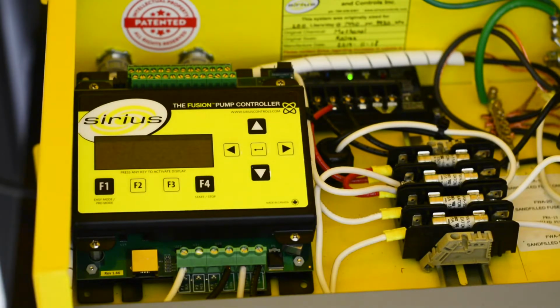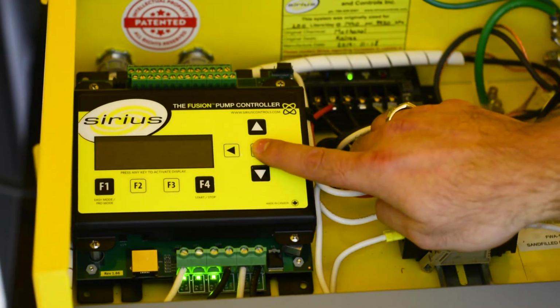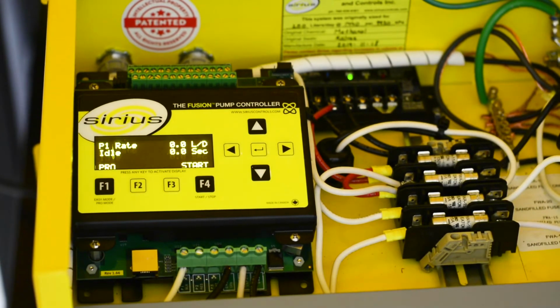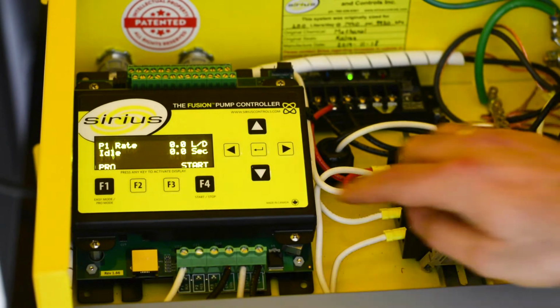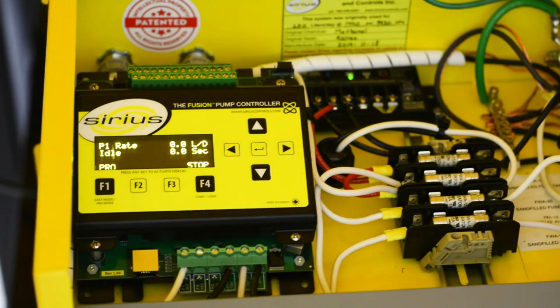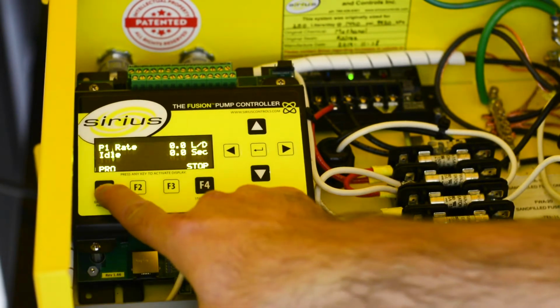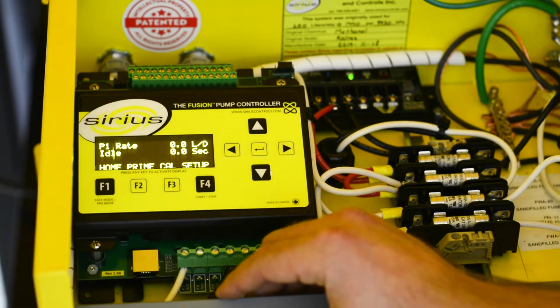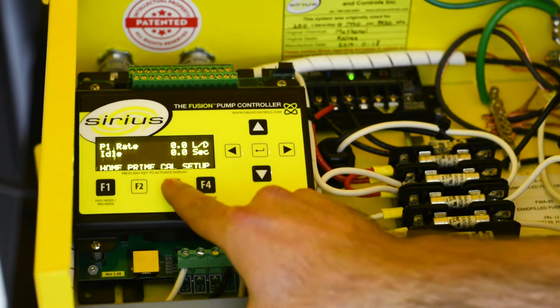To calibrate the pump, push any button to wake up the controller. Ensure the controller is enabled. You should see Stop above the F4 button. Now hold F1 to enter Pro mode. Then push F3 to start the calibration.